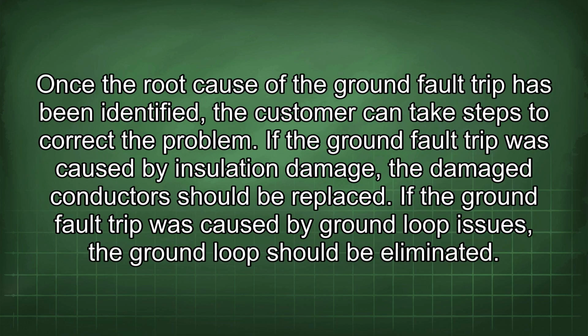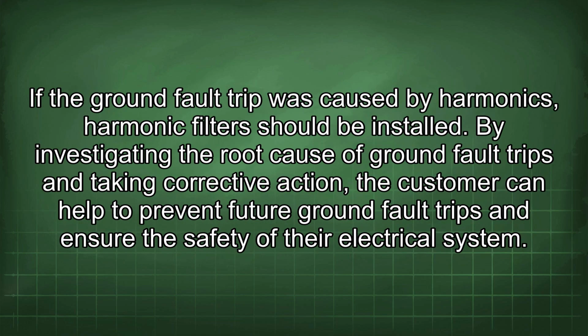Once the root cause of the ground fault trip has been identified, the customer can take steps to correct the problem. If the ground fault trip was caused by insulation damage, the damaged conductors should be replaced. If the ground fault trip was caused by ground loop issues, the ground loop should be eliminated. If the ground fault trip was caused by harmonics, harmonic filters should be installed. By investigating the root cause of ground fault trips and taking corrective action, the customer can help to prevent future ground fault trips and ensure the safety of their electrical system.